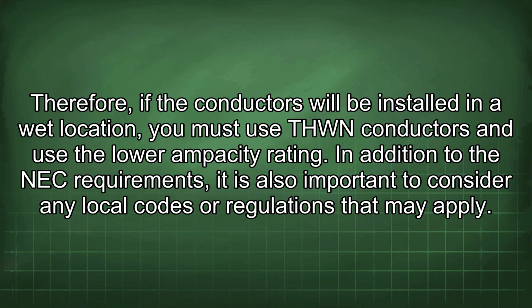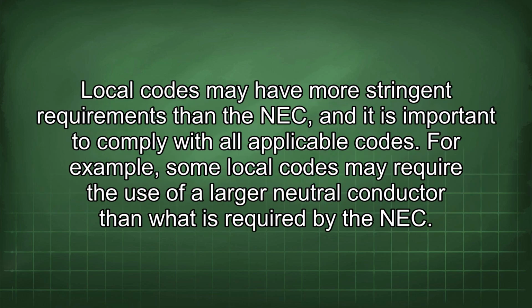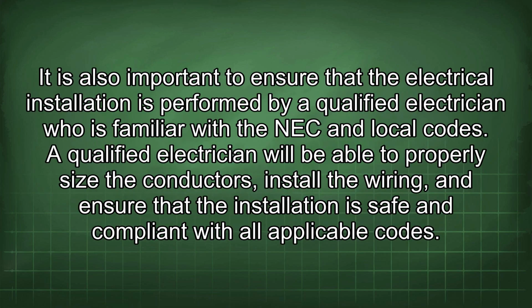Therefore, if the conductors will be installed in a wet location, you must choose THWN conductors and use the lower ampacity rating. In addition to the NEC requirements, it is also important to consider any local codes or regulations that may apply. Local codes may have more stringent requirements than the NEC, and it is important to comply with all applicable codes. For example, some local codes may require the use of a larger neutral conductor than what is required by the NEC. It is also important to ensure that the electrical installation is performed by a qualified electrician who is familiar with the NEC and local codes. A qualified electrician will be able to properly size the conductors, install the wiring, and ensure that the installation is safe and compliant with all applicable codes.